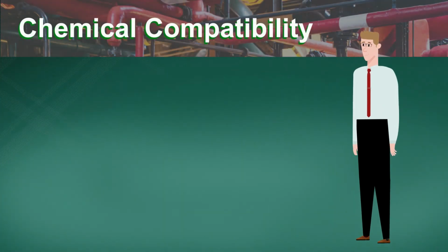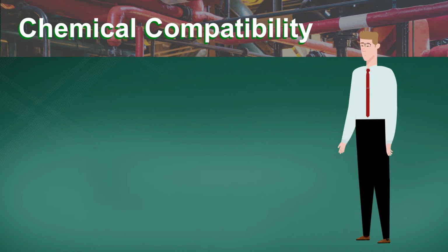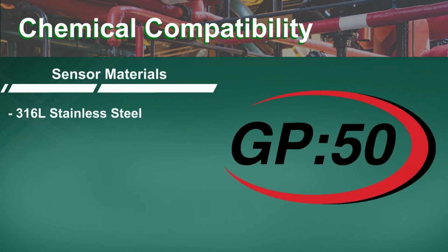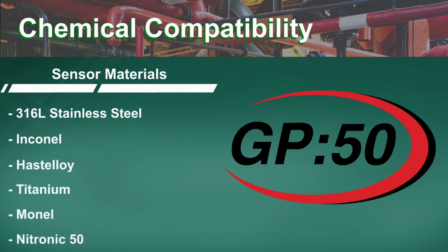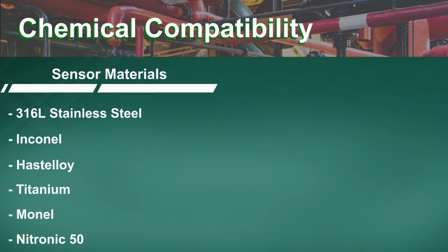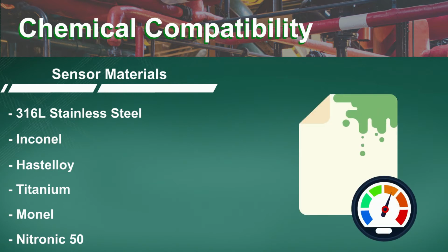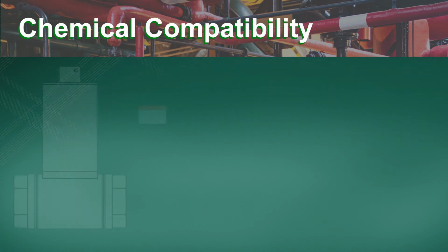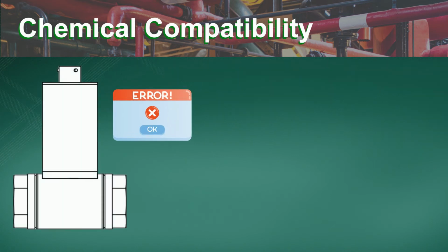Some chemicals used in the application may not be compatible with some sensor materials. GP50 provides sensor materials in either 316L stainless steel, Inconel, Hastelloy, titanium, Monel, and Nitronic 50 to meet many different process media demands. Incompatibility may cause drift issues where the chemical etches the sensor and slowly causes an increase in output. The chemical could also attack the sensor and cause a catastrophic failure to happen.